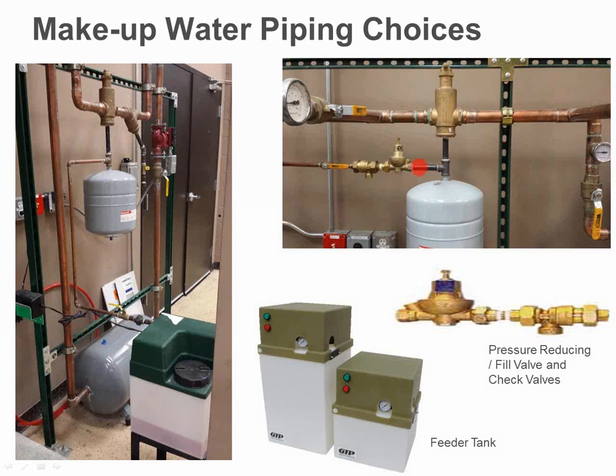The reason for 12 psi basically has to do with math, but basically most buildings, when you get to your 2 flats, 3 flats, even 6 flats with 3 apartments with 3 levels, you get up that baseboard, it might be 20-some feet. If I have 12 pounds of pressure, I have more than enough water all the way up to the top of that system. So that's where now my circulator is a true circulator. We're not pumping water up there. This valve does that. It maintains that whole system.